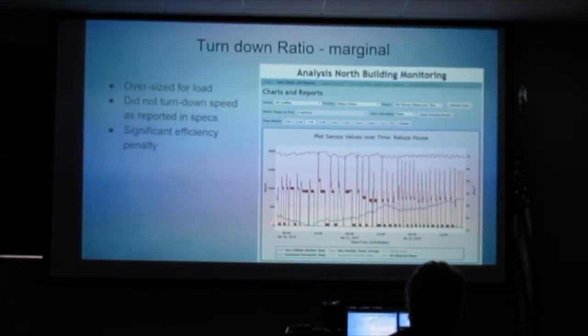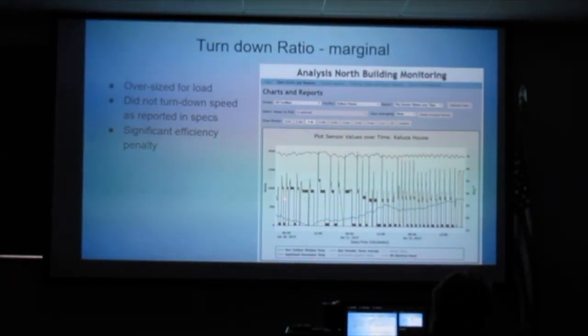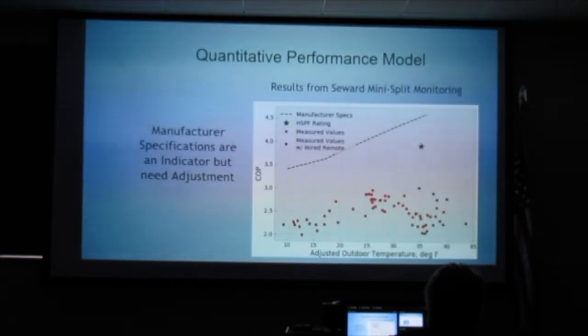This is kind of what was happening with that heat pump. It would cycle, purr along for a little bit, then lose it, turn off, turn on, turn off, turn on, and never really found that comfortable spot. They're supposed to be able to vary output based on your load, and magically find where they can put out the exact amount without raising or lowering the indoor temperature. Well, it just did not like my house.